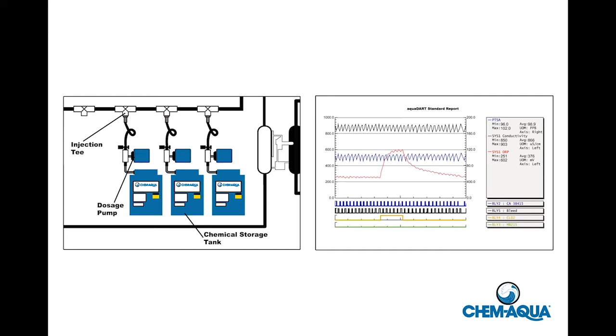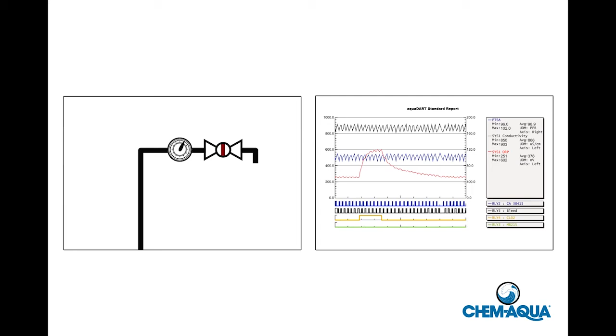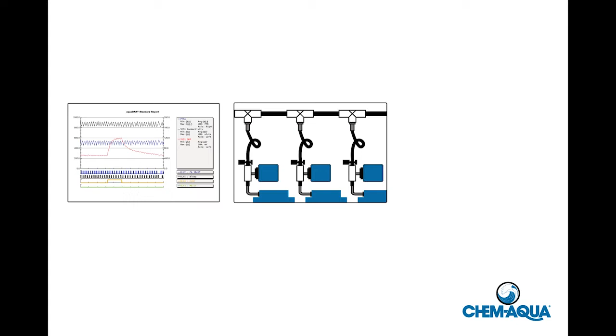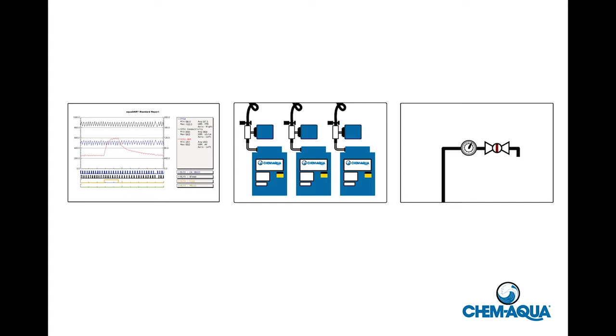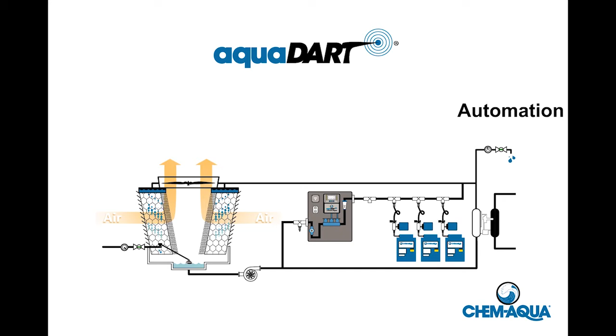Microbiological control is maintained and monitored using custom ORP link timers to ensure proper biocide dosages. Water usage is minimized using conductivity control to ensure proper cycles of concentration and blowdown rates are maintained. Aquadart provides online feed and control verification of vital system chemistries to minimize water-related problems and inefficiencies. Wireless and direct connection to the cloud allows remote system monitoring and call-out alarms for upset conditions. When treatment levels are out of range, chemical pumps stop pumping, chemical drums run dry, blowdown valves malfunction, and more, Aquadart triggers alarms for immediate notification and rapid response.